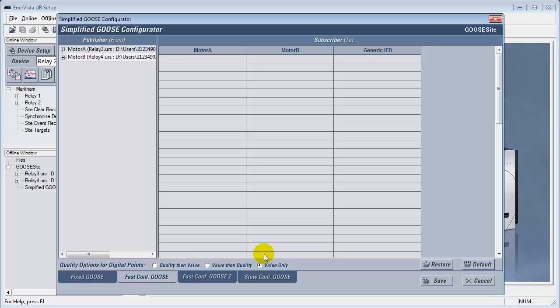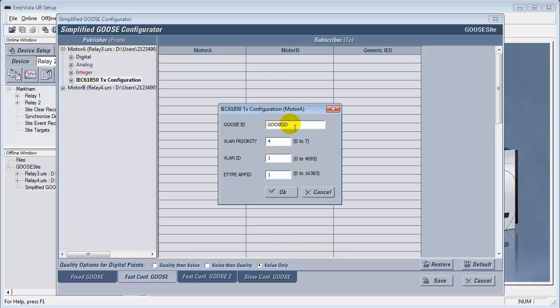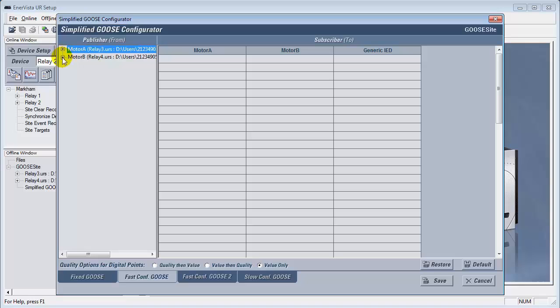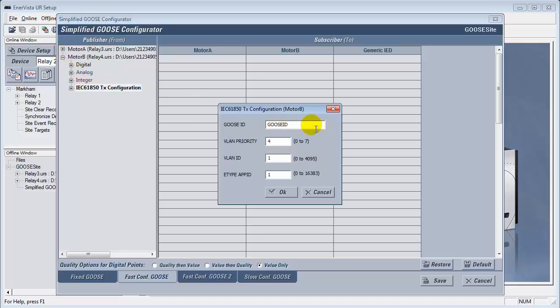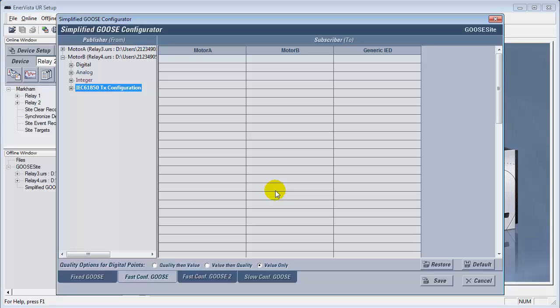For Step 5, in the Fast Configuration Goose tab, you must configure the IEC 61850 tab again. Additionally, we must select values to be used in 61850 communication between the both relays. Note that only high priority digital signals should be placed in Fast Configuration Goose 1 and 2. Slow Configuration Goose is used for low priority digital and analog signals.